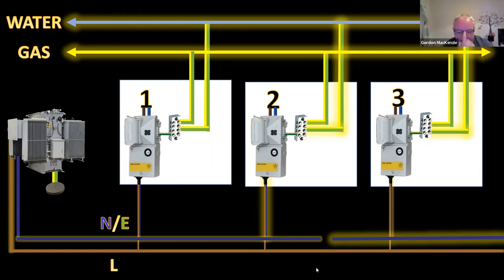No, it's accurate, Paul, absolutely accurate. I think the key part to explain is the separation of the conductors in the domestic property, the live, neutral and earth, and then they're combined at the point of connection to the network. One interesting part is that your RCD simply doesn't see neutral current diversion. It will pass through the RCD, come into the point of connection, and then find its way onto the pipe. So it doesn't behave like a fault, it's just a simple return path.